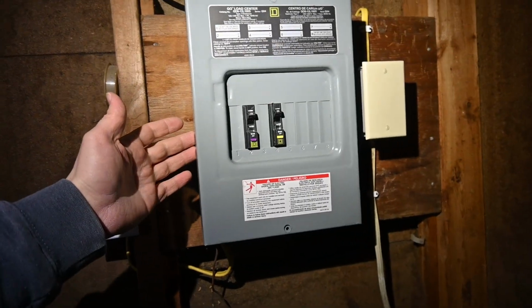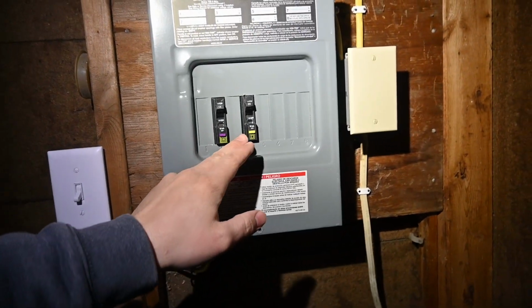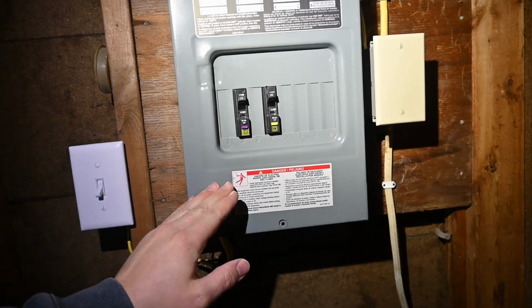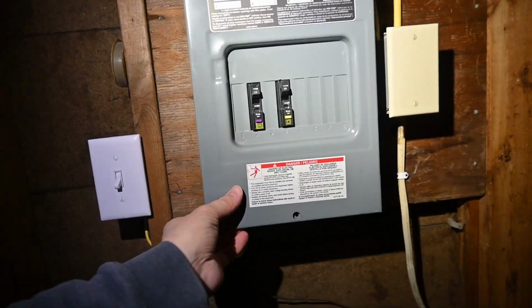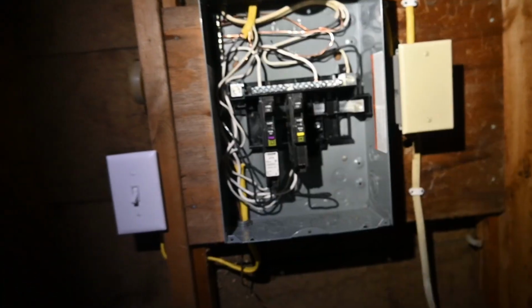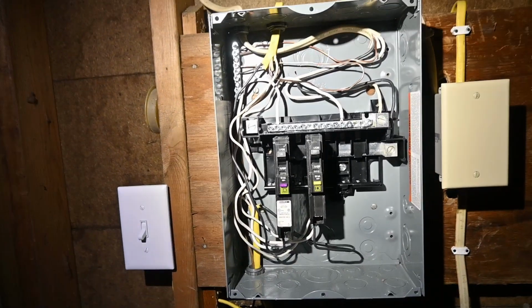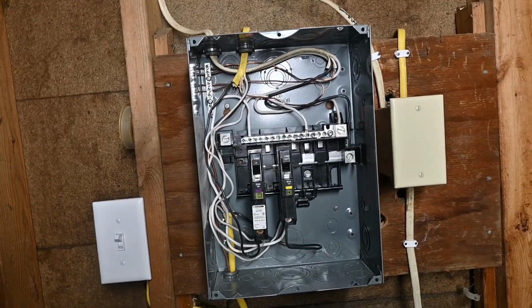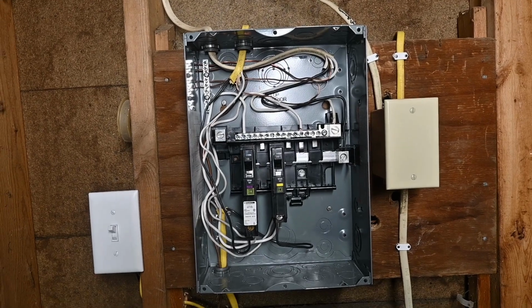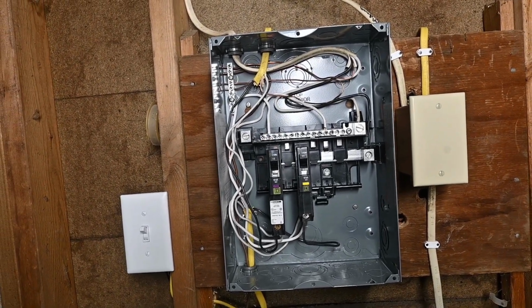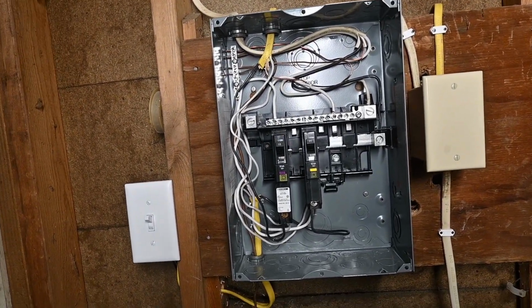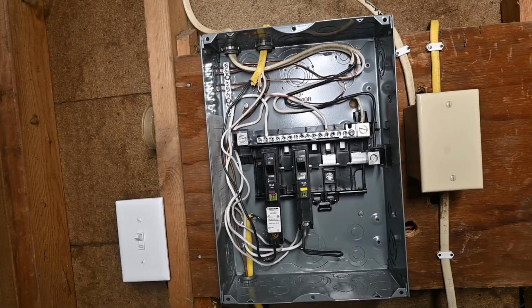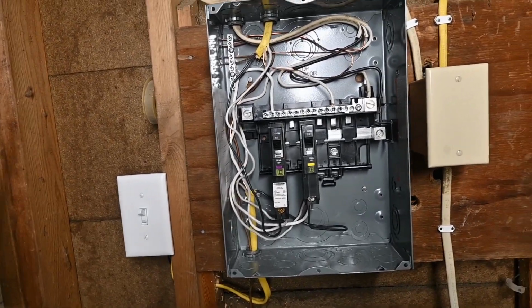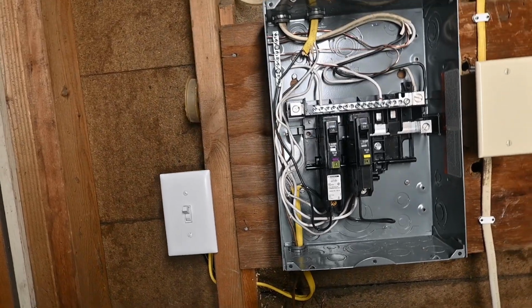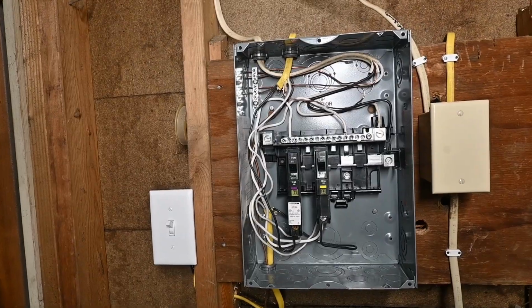The way electrical panels are designed, every other breaker pulls from every other leg of the 240 volts. When you take this off of here, we can see what's going on. I did not wire this panel myself. This is just an example of a 120 volt panel that is currently set up. Albeit this is really a 240 volt panel being used as a 120 volt panel, and I'll explain that here. So let's go through it.